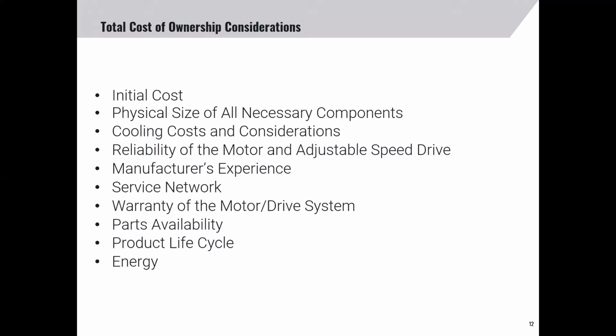And don't forget about the reliability of the cooling system. In the case of air conditioning cooling, it doesn't matter how reliable your adjustable speed drive is if the air conditioner cooler that the drive is being cooled by is not working. And speaking of reliability, as we all know, reliability is directly tied to uptime. When your drive or motor is down, there is a cost to your company in lost production. In many applications, the cost of lost production can easily dwarf the initial purchase price and is thus an extremely important consideration. The reliability of both the adjustable speed drive and the motor should be considered.